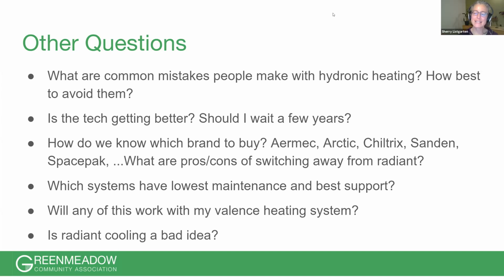Well, doesn't Sanden use CO2 and that gets pretty hot? Right, so let me clarify. The Sanden uses CO2, which is really good for domestic hot water. It can also generate high temperatures up to 170 degrees. The problem with this technology is it doesn't like warm return temperatures.